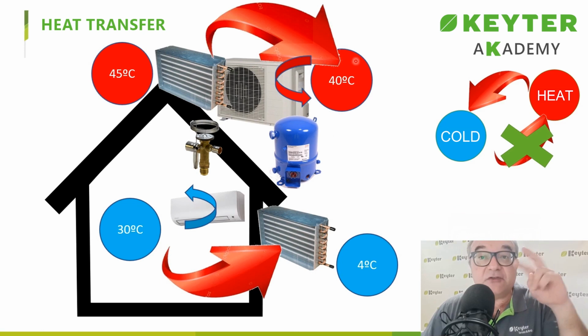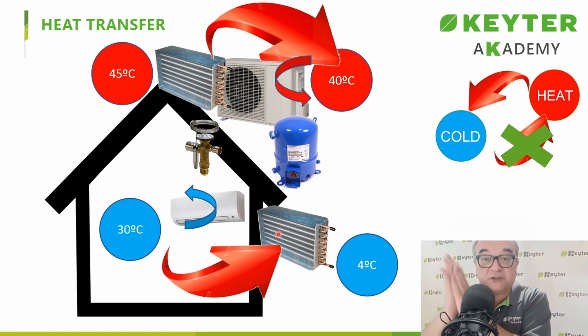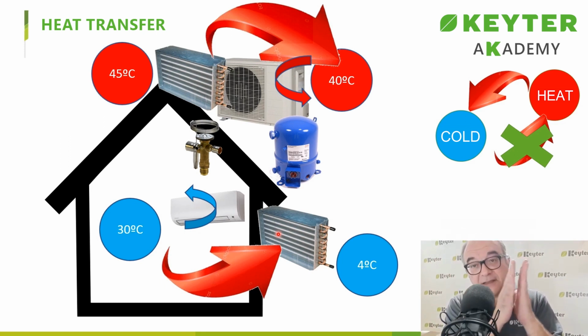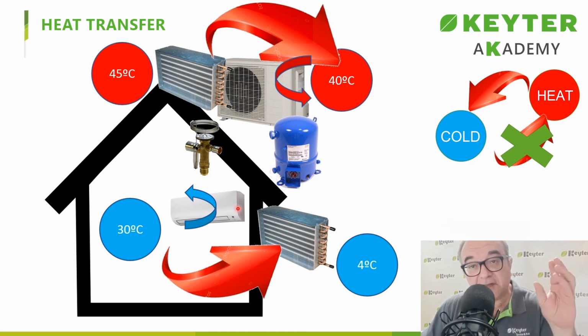How would the heat pump be reversed? Well, what we do is place this battery here and place this battery here. We turn it around, no problem. What occurs when we have, for instance, a chiller? Instead of an air battery, we would have a plate exchanger, where the evaporating freon circulates. It will not come into contact except with a metal plate in the middle, and on the other side, water would circulate, and we cool the water to lower its temperature. So this is the principle of the heat pump that works for both the split unit in your house and for a chiller, as well as for a rooftop or any equipment that works in heat pump mode.